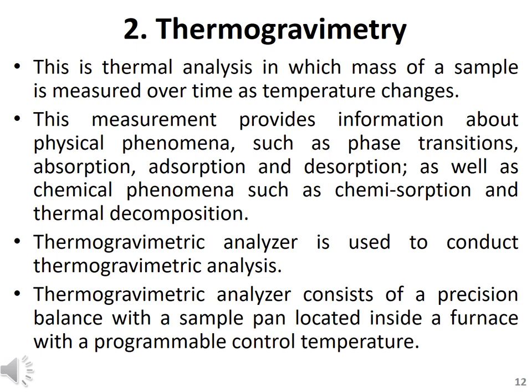The temperature is generally increased at a constant rate to incur a thermal reaction. The thermal reaction may occur under a variety of atmospheric conditions including ambient air, vacuum, inert gases, oxidizing or reducing gases, and corrosive gases — all of these atmospheres can be used to perform thermogravimetric analysis.